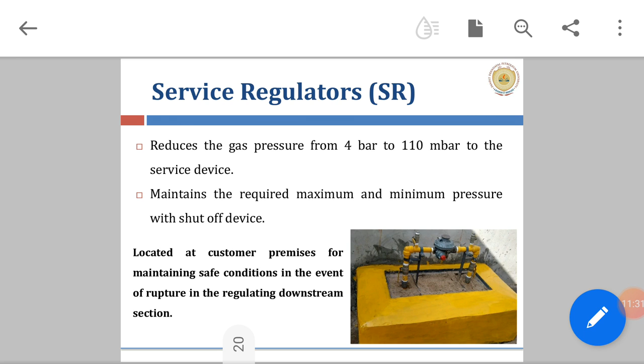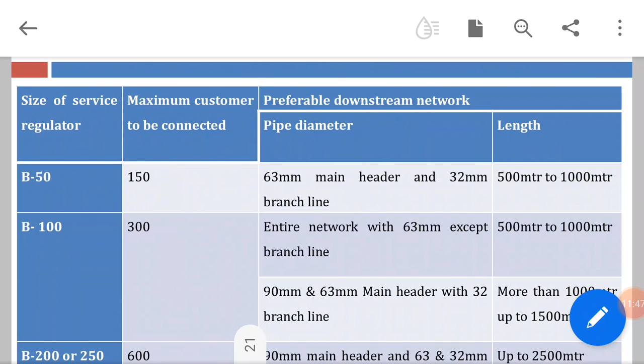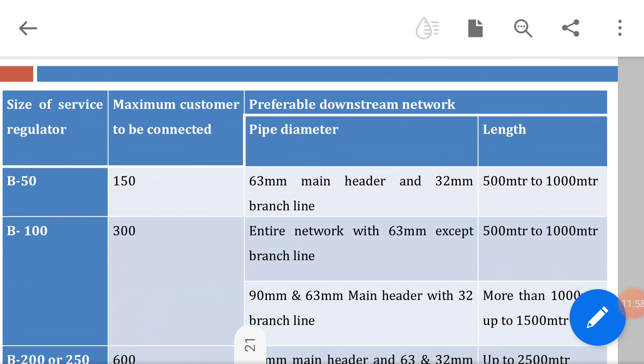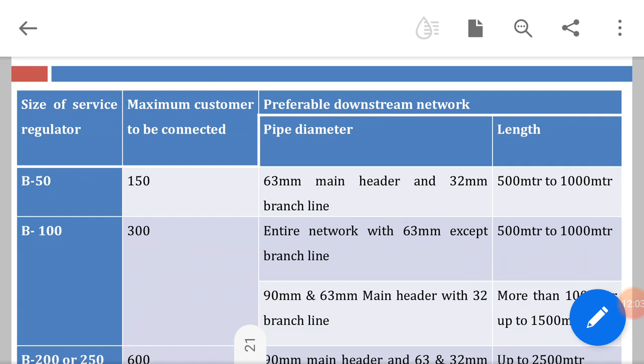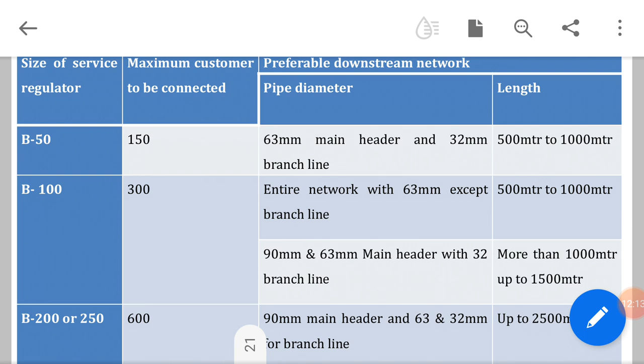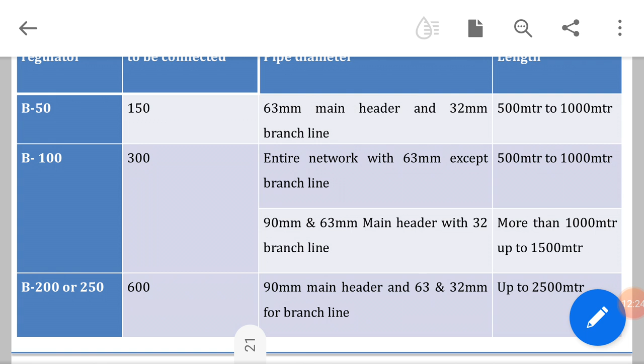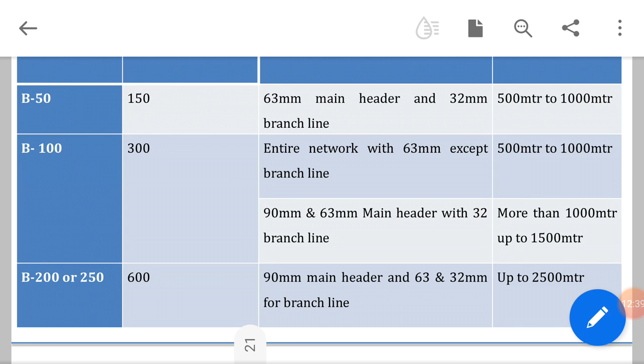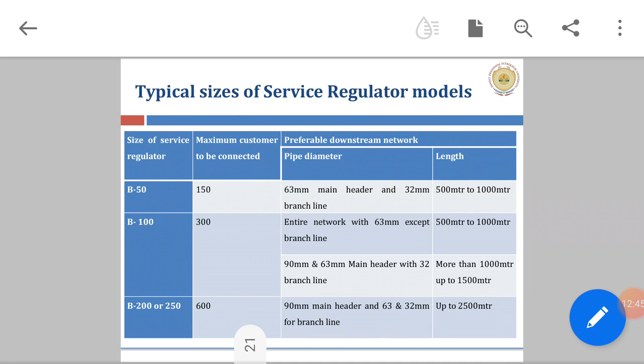Now in this table we can see the typical sizes of the service regulator model. We can see sizes of 150, 300 and 600. These are known as B50, which has 150 maximum customers to be connected. The preferable downstream network pipeline diameter is 63 mm main header and 32 mm branch line. The length is 500 meter to 1000 meter. The B100 is 300 maximum customers to be connected. Entire network with 63 mm except branch line, 500 meter to 1000 meter is the length. And then we have the 90 mm and 63 mm main header with 32 mm branch line, more than 1000 meter up to 1500 meter is the length. And the last one is B200 or 250, which can cater to the needs of 600 customers. 90 mm main header and 63 and 32 mm for branch line, up to 2500 meter is the length of this typical service regulator model.